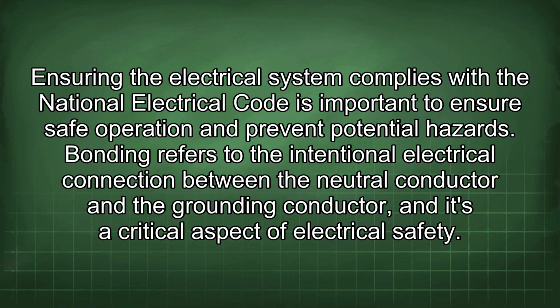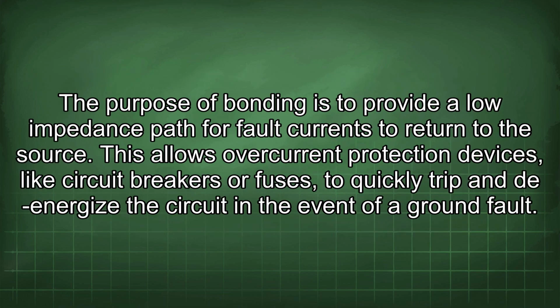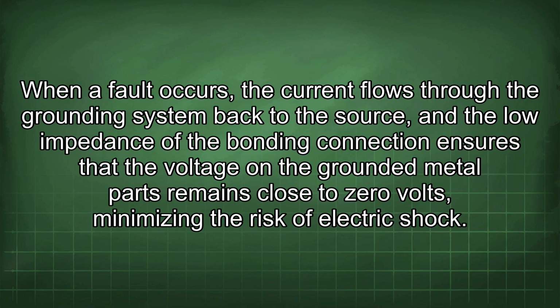Bonding refers to the intentional electrical connection between the neutral conductor and the grounding conductor and is a critical aspect of electrical safety. The purpose of bonding is to provide a low impedance path for fault currents to return to the source. This allows overcurrent protection devices, like circuit breakers or fuses, to quickly trip and de-energize the circuit in the event of a ground fault.